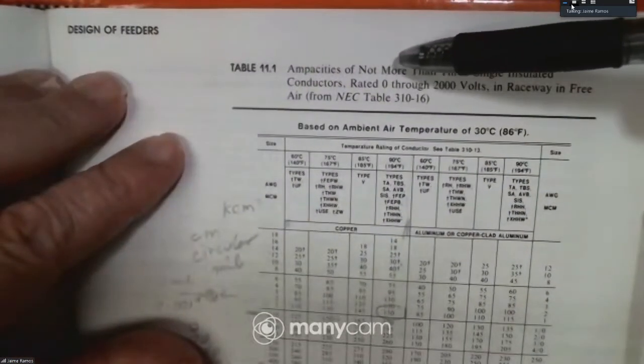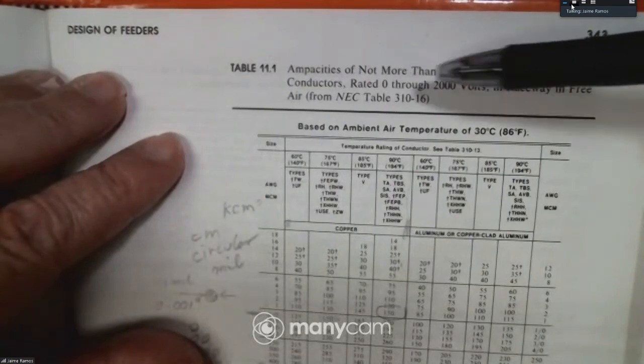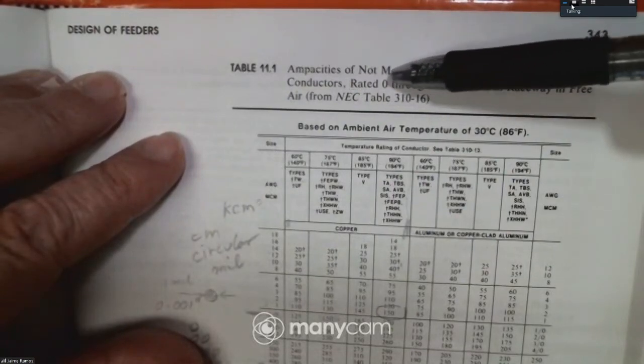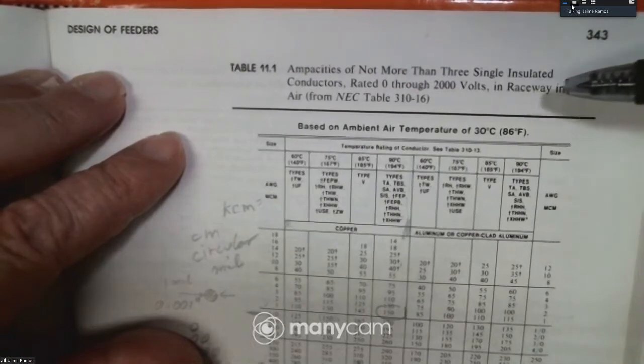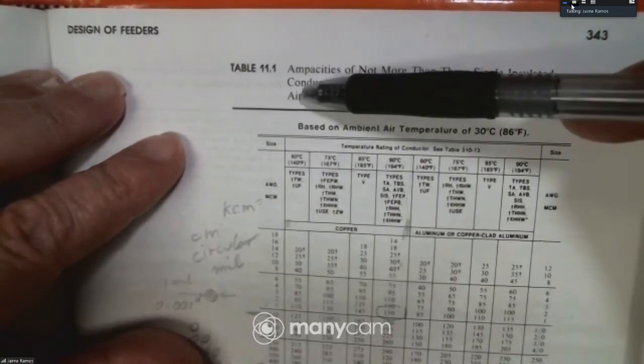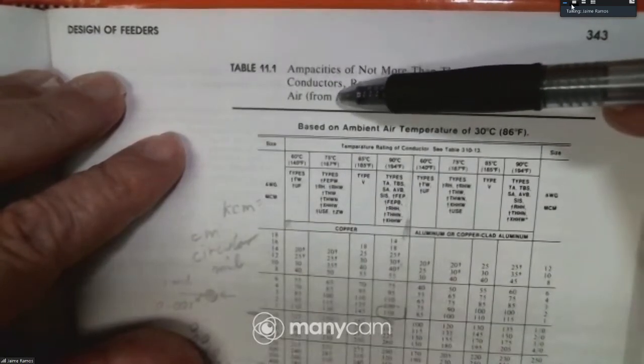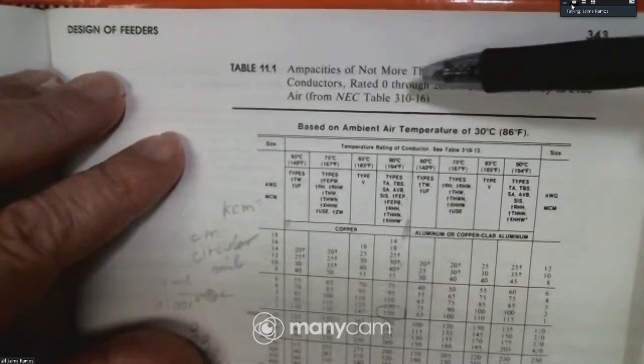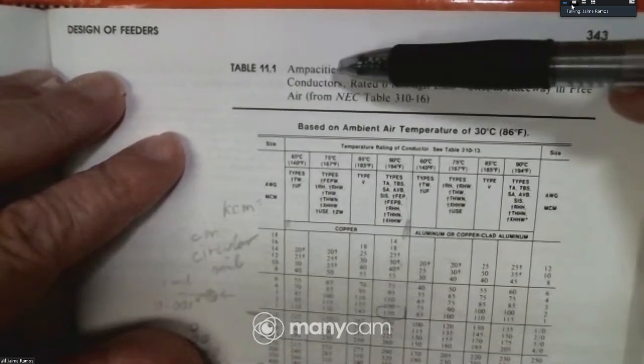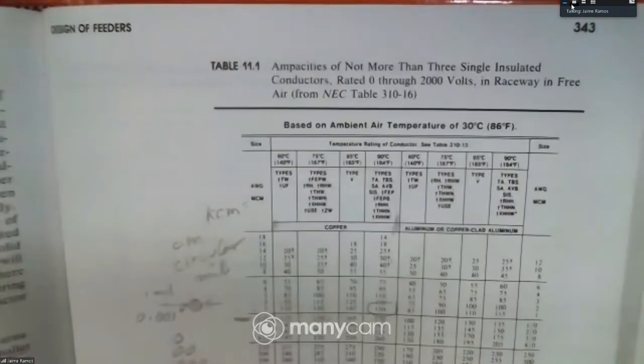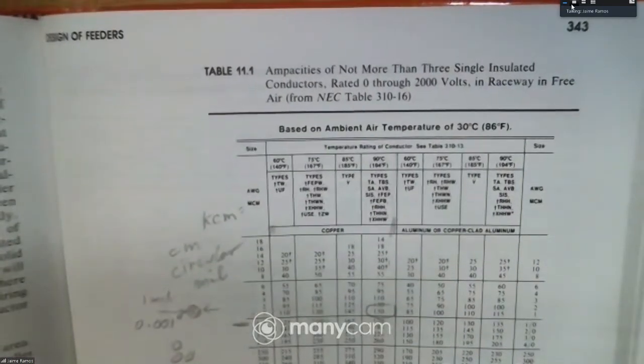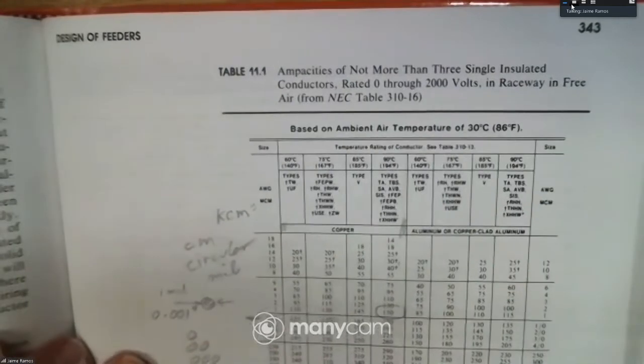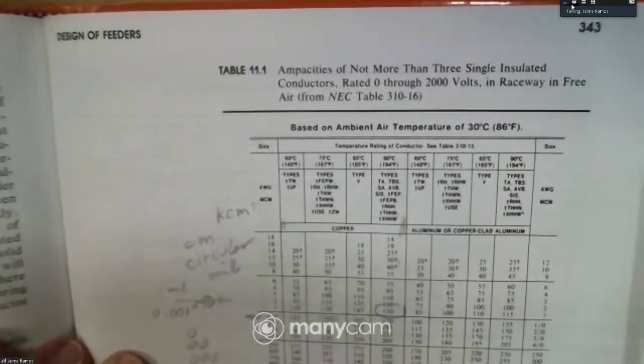Okay, and then all these numbers are called the ampacities. So what ampacities of not more than 3 single insulated conductors rated from 0 to 2000 volts in raceways in free air from the National Electric Code table. Okay. So, and then what is ampacity? Ampacity is the normal capacity. By normal, we mean standard temperature that the conductor can carry.